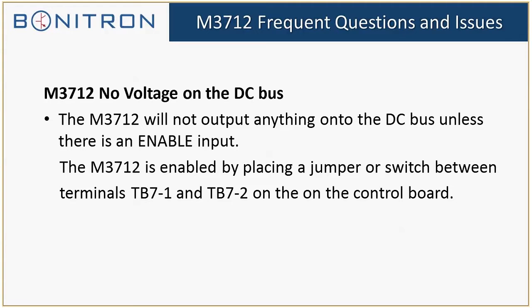This can either be done with a jumper. I would say 99% of people just go for the jumper on those terminals, TB7-1 and TB7-2 on the control board, or else you can control the M3712 through your PLC. But it seems that for most of our customers, they use a single phase power supply in locations that are remote or very rural. So they mostly just want it operating all the time as soon as they give it power. So they usually just place that jumper on those terminals.